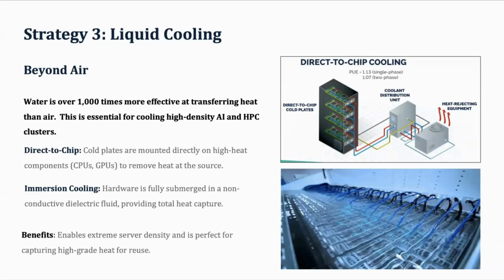So this method has a very good heat absorbing capability. It is used for very high performance computing, and these days gaming and everything. The cold plate is directly mounted over the chip, and the refrigerant or chilled water is directly supplied over that, and the cold plate will absorb the heat being generated by either the CPU or the servers. In that way, the cooling is achieved at the local level.